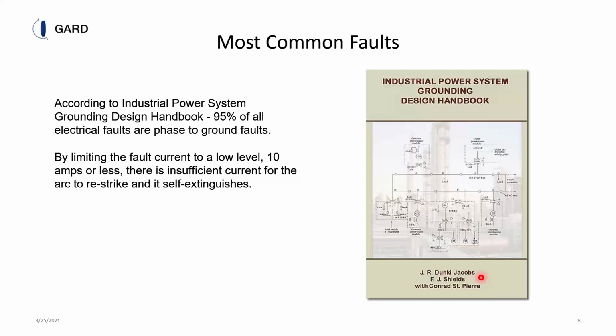If you have a solidly grounded system and you have a ground fault, you have to imagine that you have a tremendous amount of energy deteriorating the insulation around the point of the fault. So you can have molten steel, molten copper, all kinds of debris deteriorating the insulation, because in 600 volts or below, or anything less than 1,000 volts, the primary insulation is air. If you deteriorate the air, then you deteriorate the insulation, and you can have a phase-to-phase and or 3-phase fault, which all started from a single phase to ground fault.